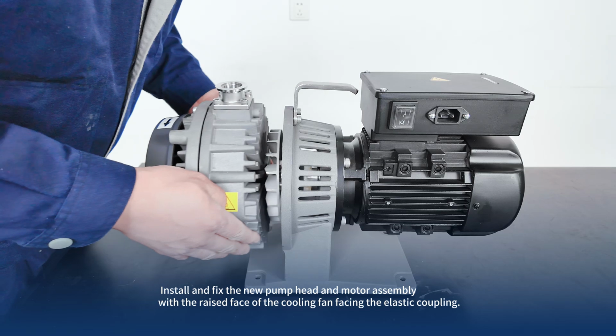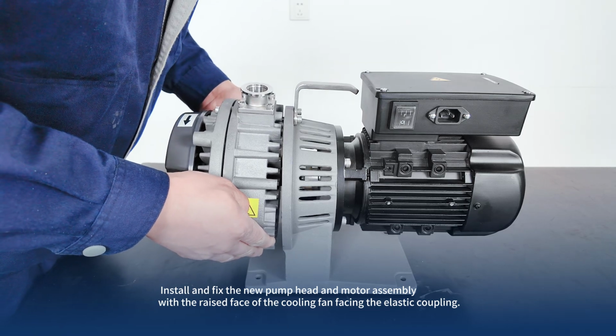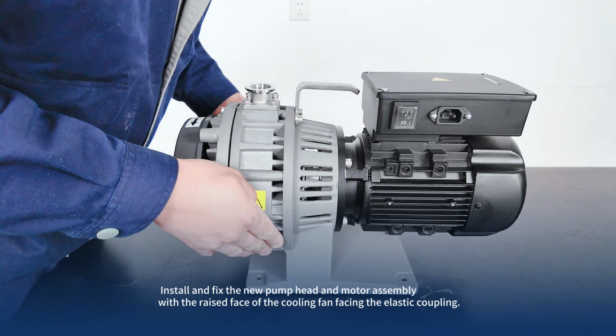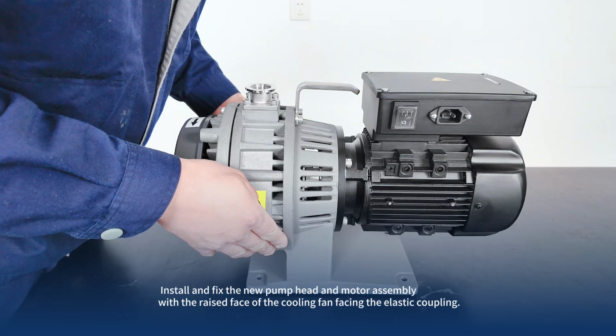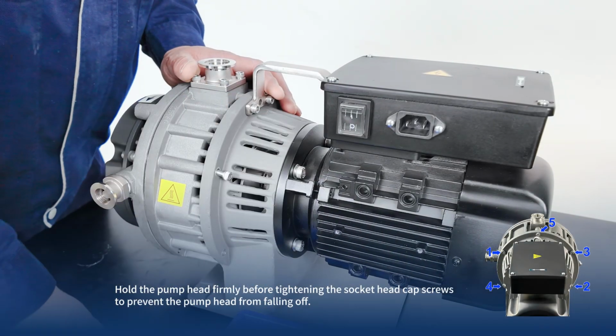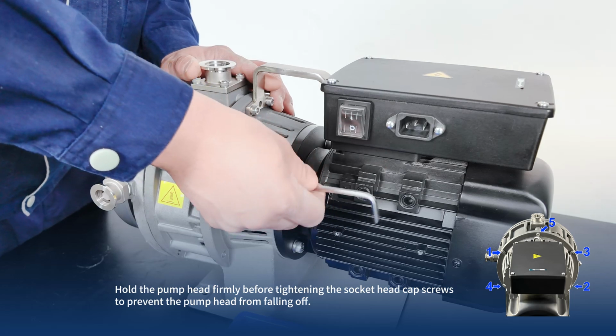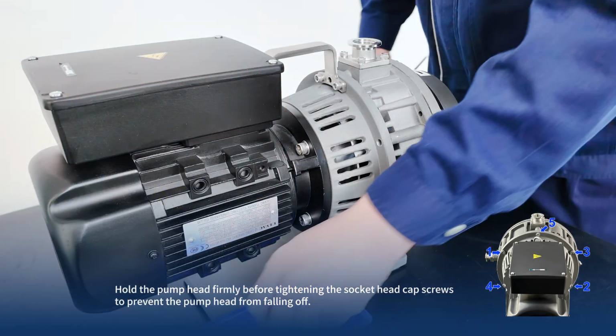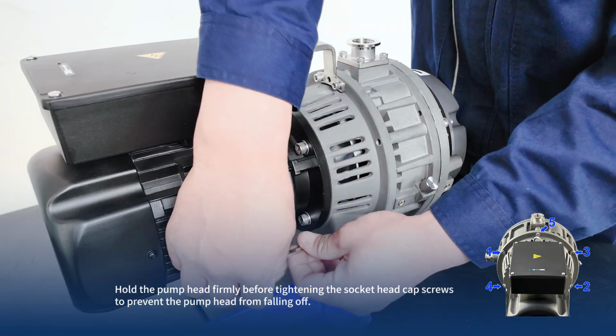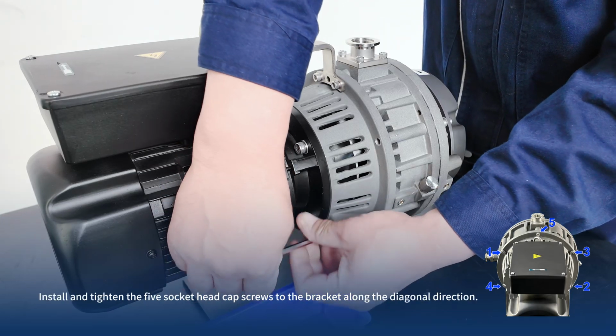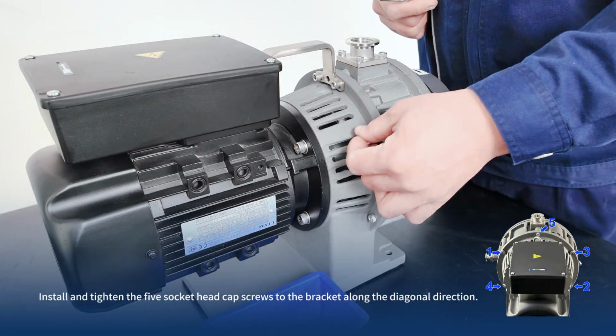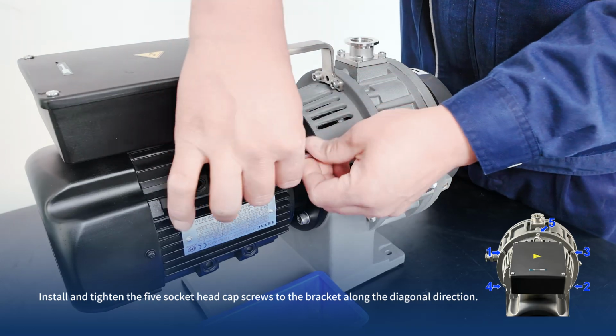Install and fix the new pump head and motor assembly, with the raised face of the cooling fan facing the elastic coupling. Hold the pump head firmly before tightening the socket head cap screws, to prevent the pump head from falling off. Install and tighten the 5 socket head cap screws to the bracket along the diagonal direction.